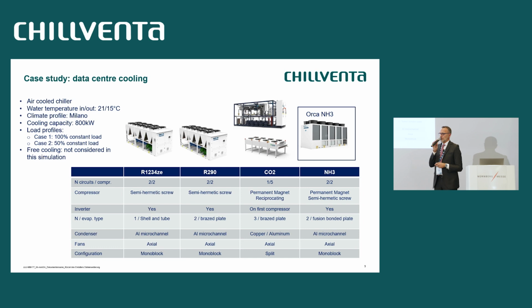So let's talk about one specific application. As I said before, ammonia is well known in industrial refrigeration, but we believe in the possibilities of this refrigerant also outside this sector. And one example is data center cooling. So we decided to run a simulation with our internal simulation tools of a data center in Milan. So we made some assumptions. The water temperature from 21 to 15, the climate profile of Milan, and the cooling capacity of 800 kilowatts. And we took two load profiles, 100% constant load and 50% constant load, which are two typical cases that can happen in a data center.